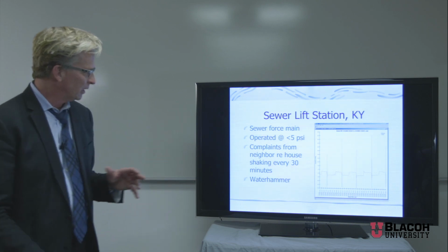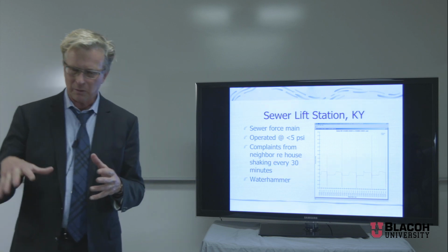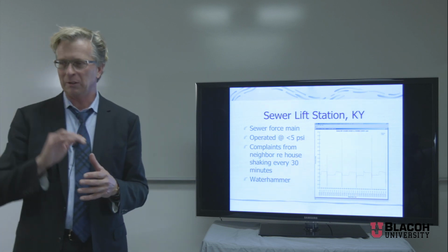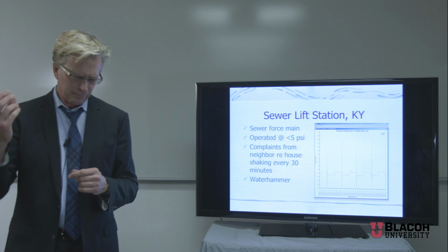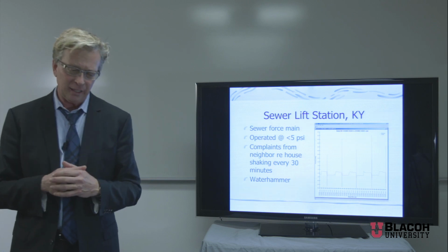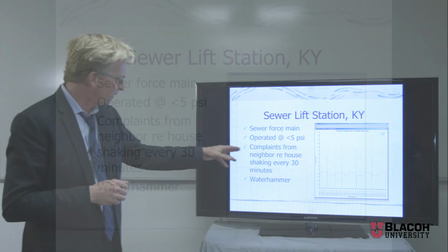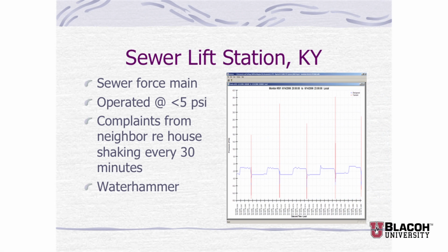Up on top of this hill, of course, we have high pressures down low and low pressures up high. We hooked up the transient monitoring data. You can see it's a very low operating pressure now, but before that, when the line would go to a full cavitation, this whole pipeline would move.